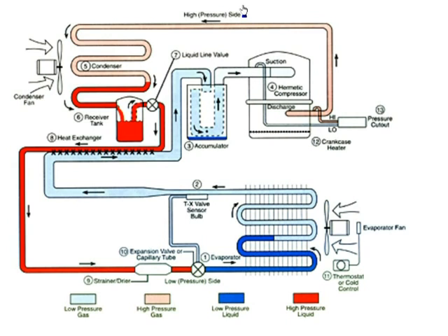Alright, so if you look at how refrigerant changes states throughout the cycle, that's the best way I can explain it. Now, as far as temperatures go, you have a high pressure liquid. It's a hot liquid refrigerant going into your TXV or your piston. Alright, now when it goes through the piston, it switches it to a low pressure liquid, and that's going to become really cold.